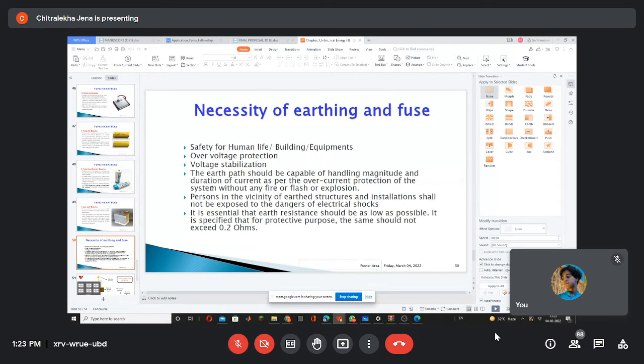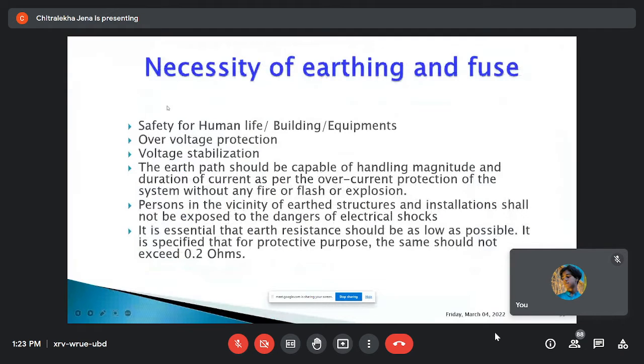The earth path should be capable of handling the magnitude and duration of current as per the overcurrent protection of the system without any fire. So what happens if you have done the earthing properly? There will be no overcurrent, and there will be no fire due to overcurrent.